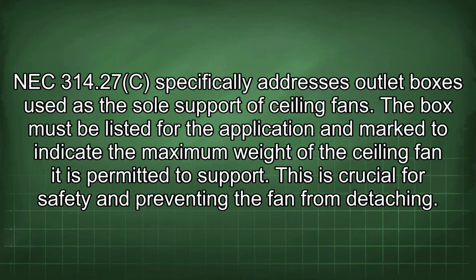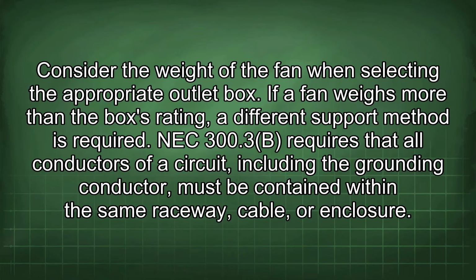NEC 314.27(C) specifically addresses outlet boxes used as the sole support of ceiling fans. The box must be listed for the application and marked to indicate the maximum weight of the ceiling fan it is permitted to support. This is crucial for safety and preventing the fan from detaching. Consider the weight of the fan when selecting the appropriate outlet box. If a fan weighs more than the box's rating, a different support method is required.